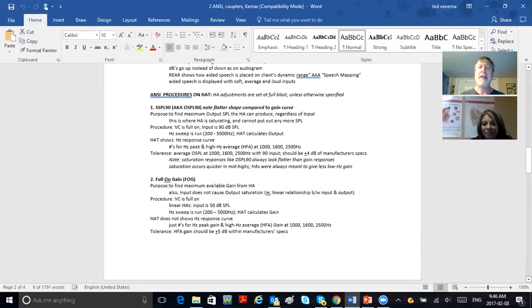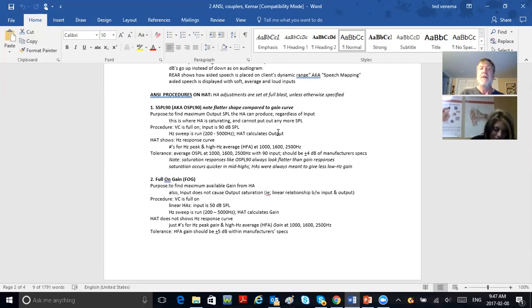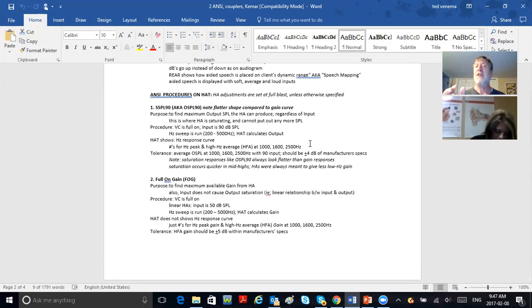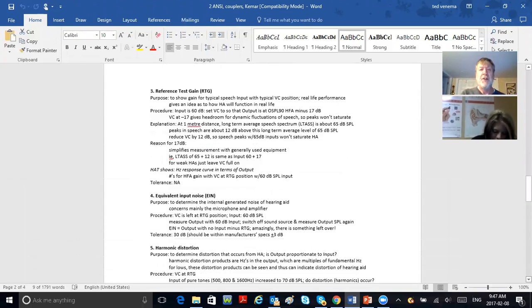The five main tests range from OSPL 90—also known as SSPL 90—as number one, then full-on gain as number two. The first is maximum output with 90 dB coming into the hearing aid. The second: leave the volume full blast but reduce the input from 90 down to 60, more like speech, and now look at the full-on gain of the hearing aid—what is its maximum gain?